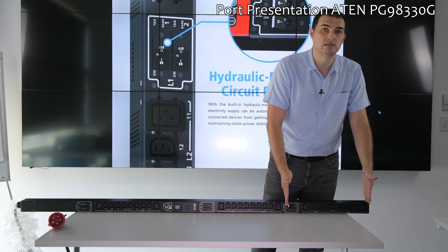This one has an allocated circuit breaker, which means if we have a problem on any of these servers and it tends to spread like a short circuit or an overload, the hydraulic magnetic circuit breaker will disconnect and prevent the error from spreading to the entire server lines covered by this product. So what we have here is 10 ports divided in 2 groups of 5, each with individual hydraulic magnetic circuit breakers that can prevent errors from spreading to other computers.